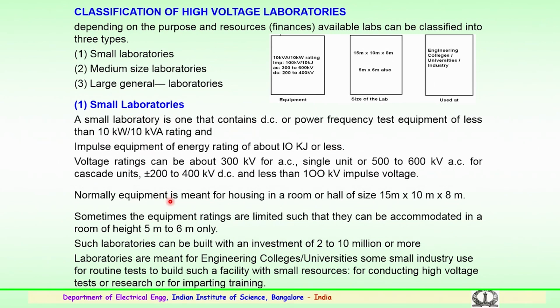A small laboratory could be one that could contain a DC or a power frequency AC equipment of less than 10 kilowatt or 10 kVA rating. And here in the small laboratories, impulse equipment could be of energy rating of 10 kilojoules or sometimes less. The voltage ratings of the equipment could be about 300 kV in case of a single transformer, or 500 or 600 kV AC. So, any of these choices. For a cascade arrangement in case of 2 or 3 units of transformer used, small laboratories could also have cascade units of plus minus 200 to 400 kV DC and less than 100 kV impulse voltages.